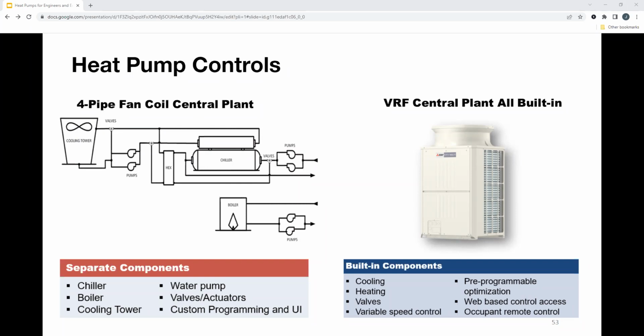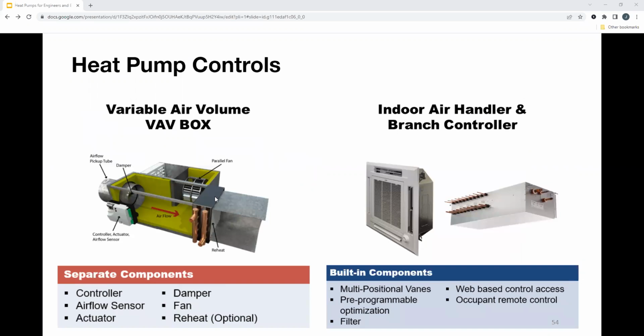But everything is built in on the VRF side, right? So your cooling, heating valves, variable speed control for the compressor, and also utilizing linear expansion valves. You can pre-program a lot of things, web-based control access, occupant remote control. All of these are built-in components to a heat pump system, though you might need to add a little extra cost onto the control side when we start putting all these pieces of equipment together. So some of these traditional systems require custom water plant controls on every component, some custom engineering and programming for each installation to optimize the system and demand loads, and then expansive ductwork and controller network installation, right? So all these are separate components: damper, fan, reheat, actuator, airflow sensor, and controller. Whereas, on the heat pump side, all of these are built-in components.